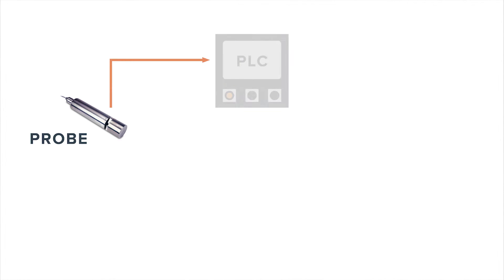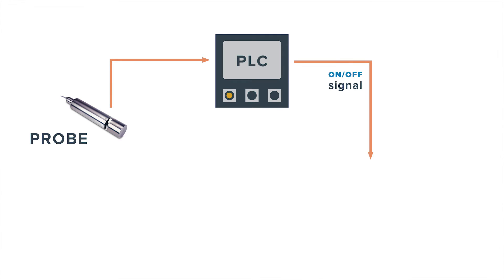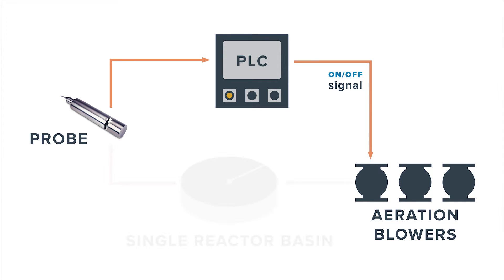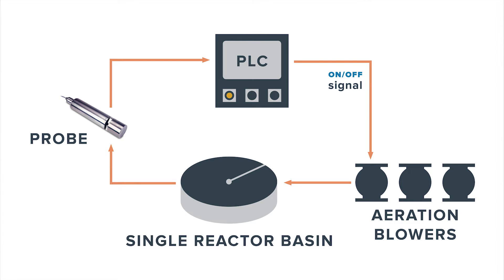The probe takes the reading and feeds it to the PLC. The PLC can then adjust the blower output accordingly for the ammonium concentration. Some of the applications for online nutrient monitoring include dissolved oxygen probes, ammonium probes, as well as phosphorus probes. These probes can help reduce blower output and improve energy efficiency, or they can be used to regulate chemical feed so that you're not overdosing or using more chemical than necessary.